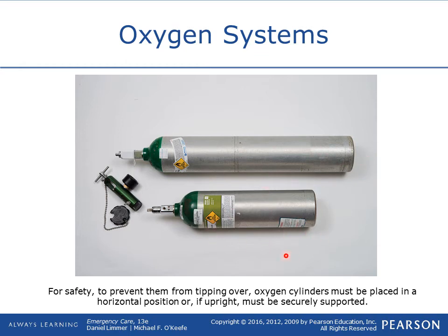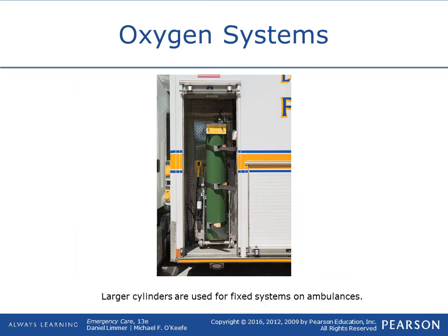And the way to tell the difference between the portable ones is these just have little valves where they've got one hole and two connecting prongs on here, and these square stems at the top. The non-portable ones have a round valve on them, with a twist top, and then this flow regulator mounts onto those. And this is the example of the non-portable one.